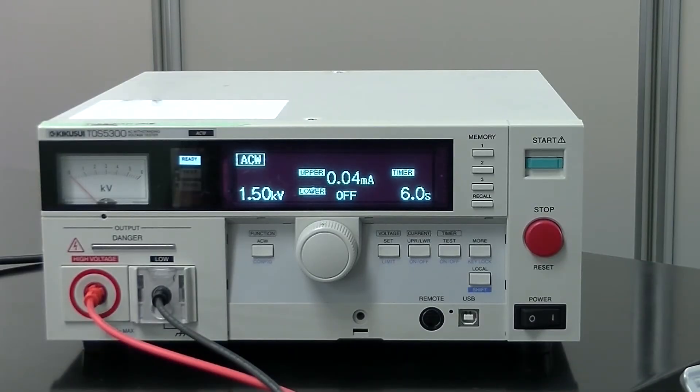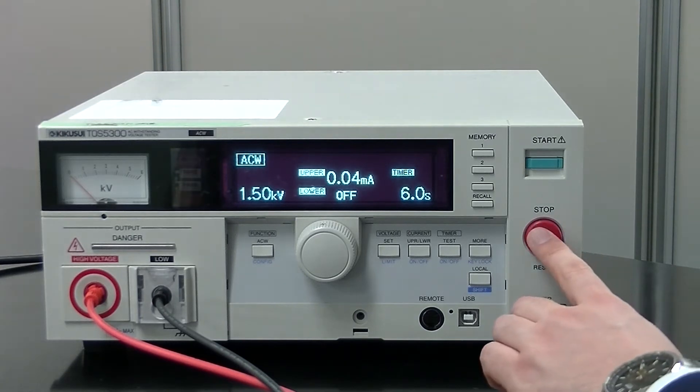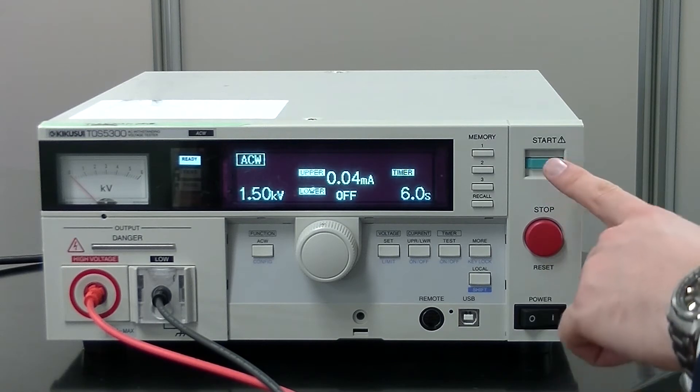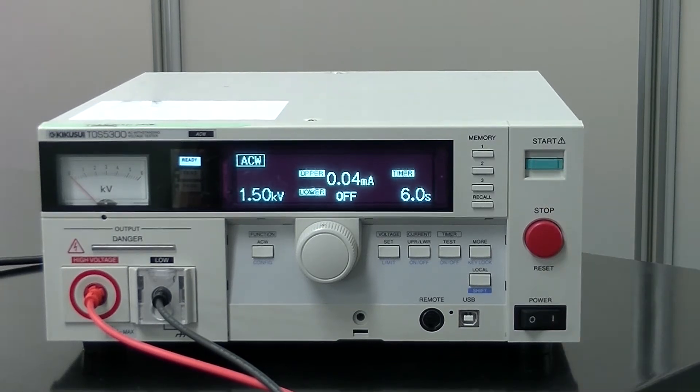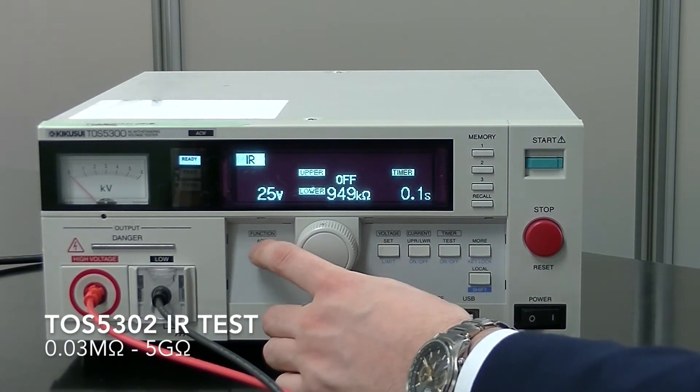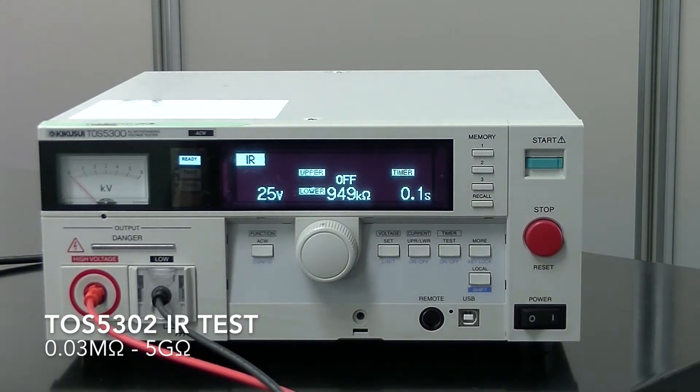This dictates how long you want to subject your DUT to the prescribed test conditions. Once your test conditions are set, you can press stop and you are ready to conduct your test whenever you press the start button. Usually, the TOS 5300 is only equipped with AC Hypot testing capabilities, but this is a modified version that has insulation resistance tests included, just like the TOS 5302. In order to set your IR settings, press the function button and set your required settings using the buttons and the dial.